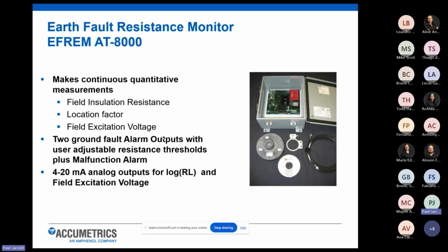The system provides the customer with two ground fault alarm outputs. We have a warning alarm output that will trip a relay and close once the value of that field resistance drops below 100 kilohms. Then we have a secondary alarm, which is our ground fault alarm, that will close a relay contact and trigger an alarm when the resistance value drops below 2 kilohms. In a healthy generator rotor that's just been rewound, or newly built or newly renovated, the resistance value of all those copper bus bars is going to be very high, in the megohm range, maybe 10 or 50 or 80 megohms. And that's good.